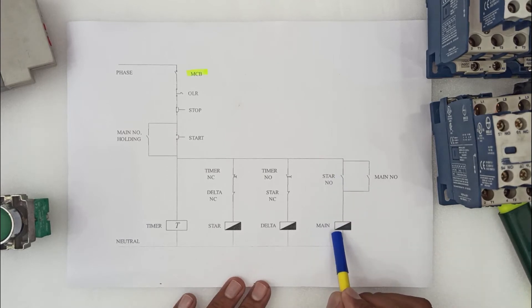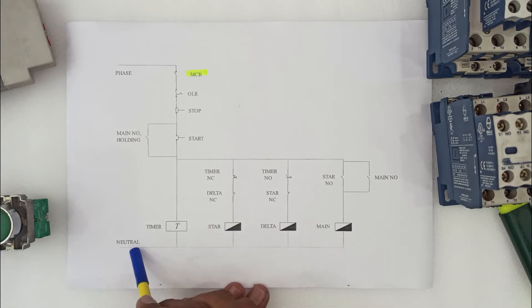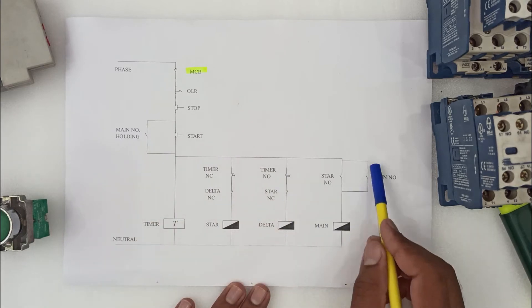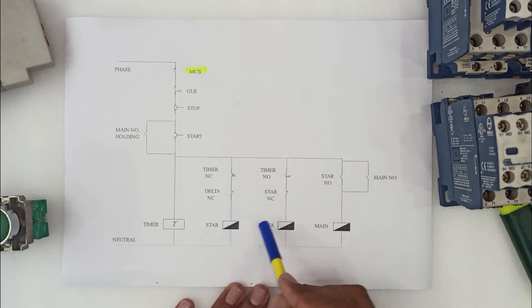The third loop is connected to the main contactor through star NO, and all neutral points of all the contactors are connected together. We have used two main contactor holding contacts: the first on the start button and the second on the star NO.